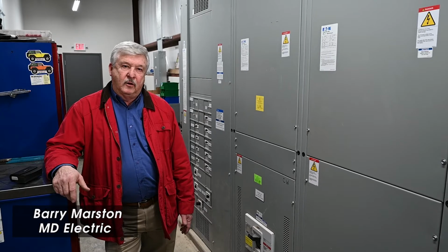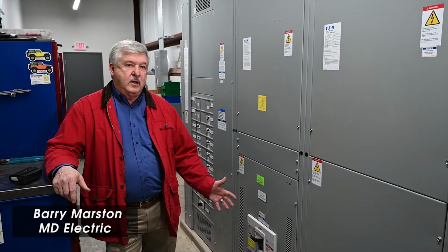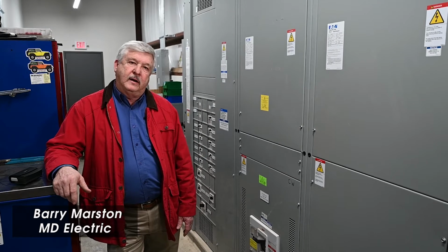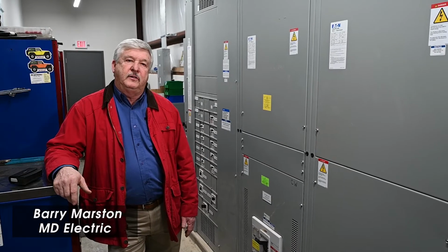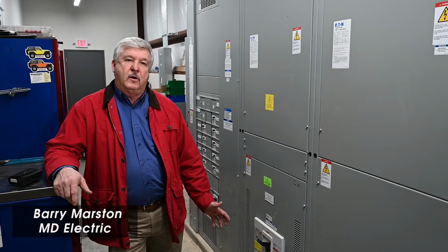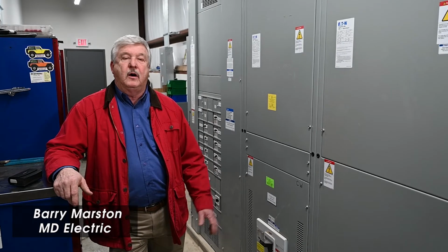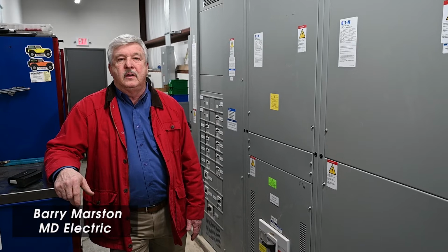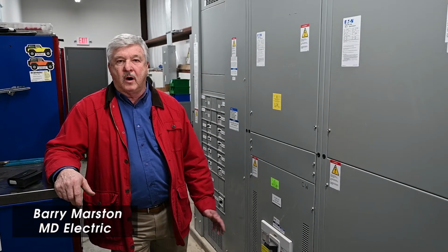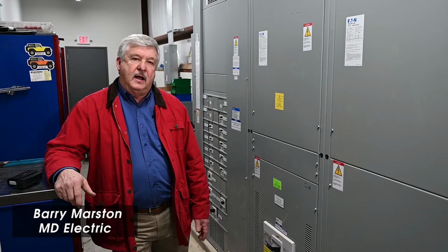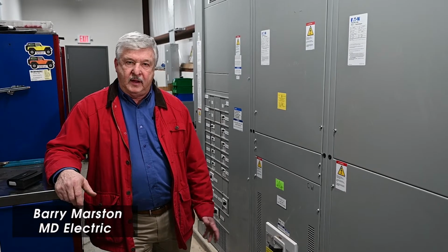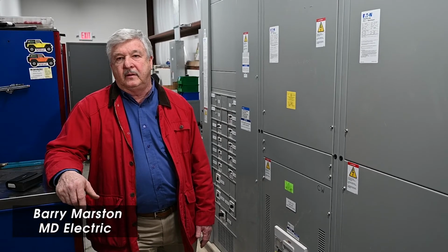As far as maintenance goes for this building, this switchgear would require periodically, like every 5 years, just going in, shutting it down for a short time and readjusting all of the lugs and such in the panel to keep them tight, where you have wire that comes in from the power company. And check each breaker and all of the lugs that the wires are attached to there. That is part of the maintenance. It would need to be done periodically just to keep it from having voltage drops.